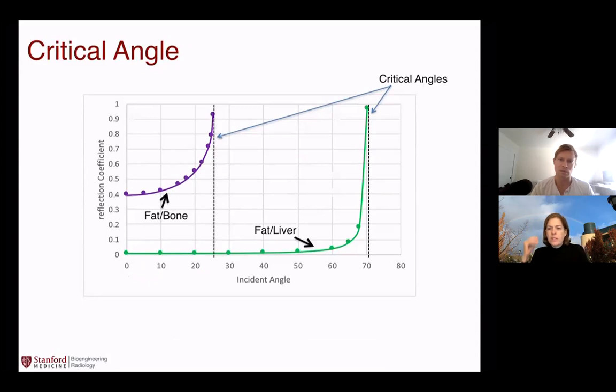It may have an effect if you may be thinking, well, I want to angle the beam, and can I angle the beam just by angling my transducer? No. That's not going to work all that well, because let's say you want to get to a part of the brain that's kind of towards the anterior part, and you want to put it right here on the temporal window and then angle the beam sort of forward. And that's not going to work, because you're going to end up now with an angle with respect to the normal.